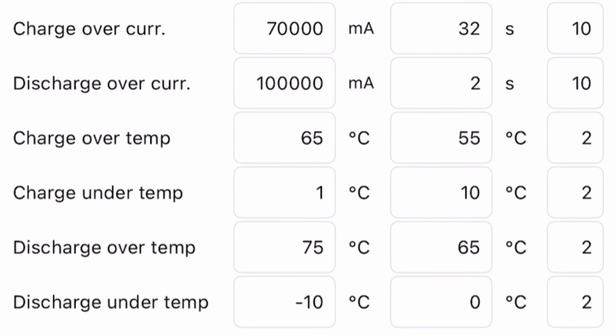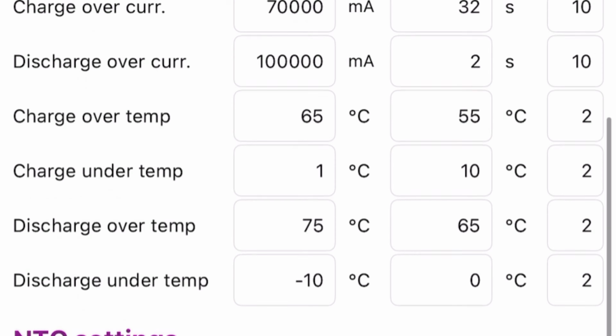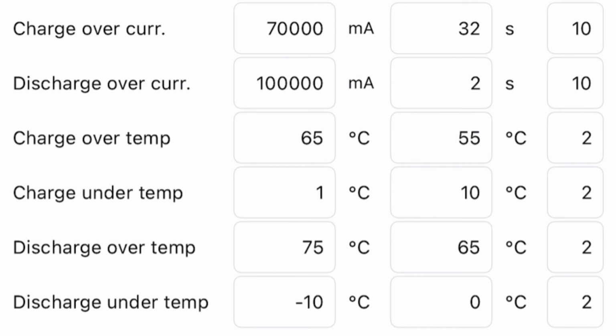The discharge undervoltage minimum temperature I have set at minus 10C to cut off the batteries, and don't turn them back on until they warm up to 0C. If you're drawing from the batteries, they will get warm, so I don't want it to cut off at 0 degrees because, one, it shouldn't have gotten that low since you're using them, and two, I don't want it to cut off when you need them, because then you can't draw power to keep them warm.